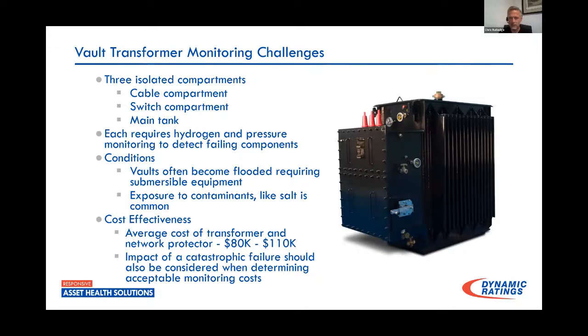And then, of course, with coastal regions, we're also looking at flooding, and that salt corrosion is also a huge issue. And then cost effectiveness, as we've already talked about, $80K is probably a little high. I don't remember the exact cost, but that is the cost of the transformer with the protector. The transformer itself, we're probably looking at somewhere in the $30,000 to $40,000 range, maybe a little less depending on the size of the transformer. I've seen these anywhere from 500 kVA up to 3,000 kVA. So that's another thing you have to consider with monitoring. Nobody's going to let you throw a multi-gas monitor on something that costs $80,000 with the multi-gas running you 30 or 40. So it's just not a realistic solution to this problem.